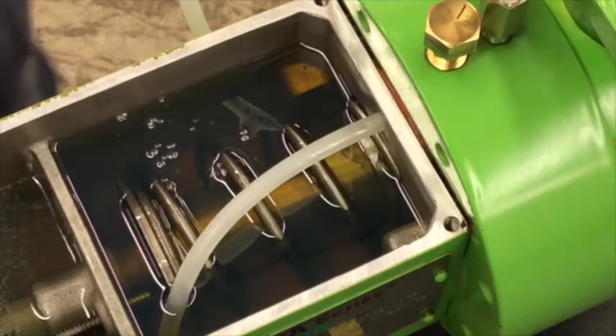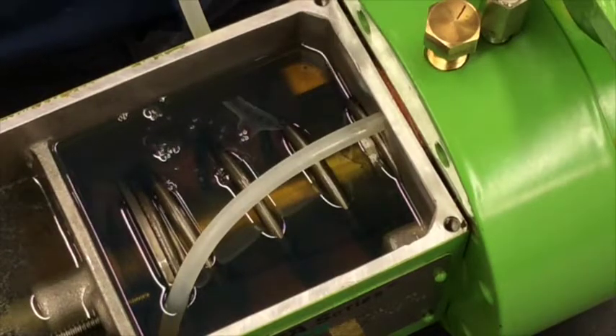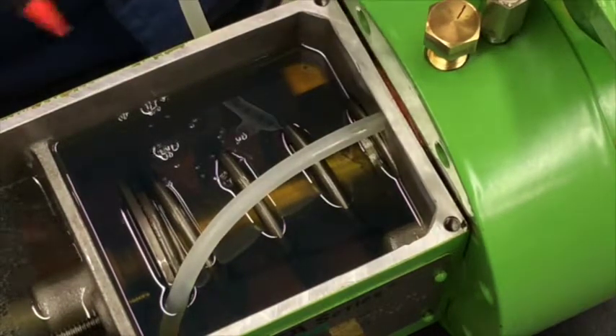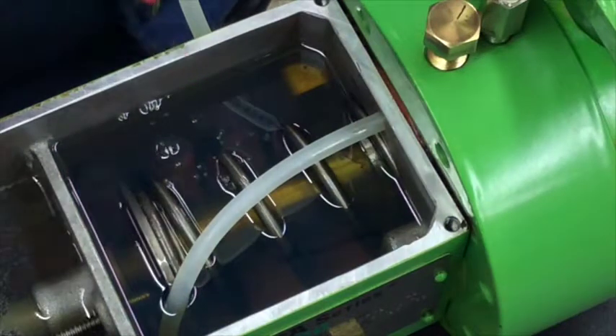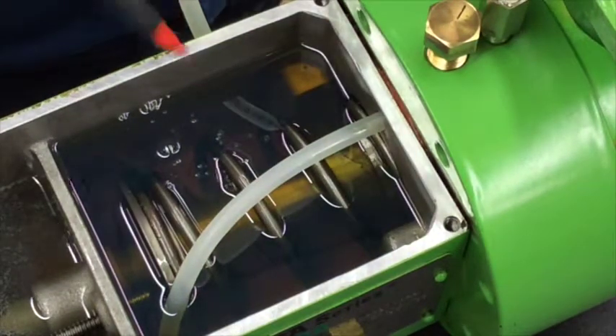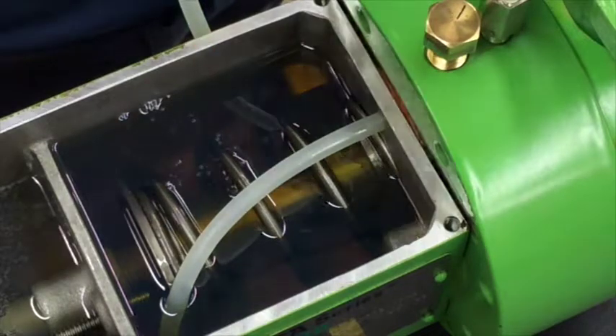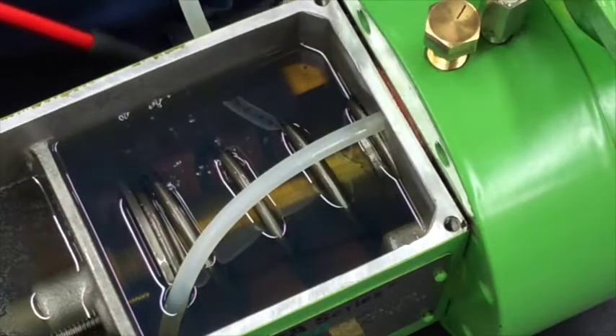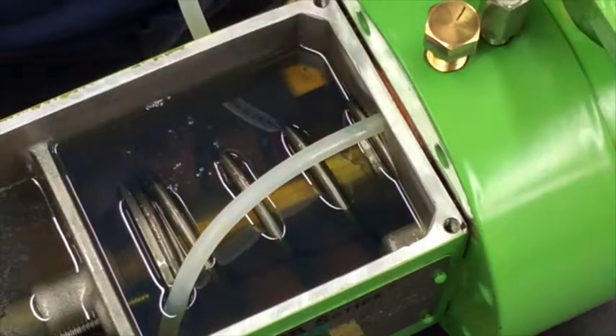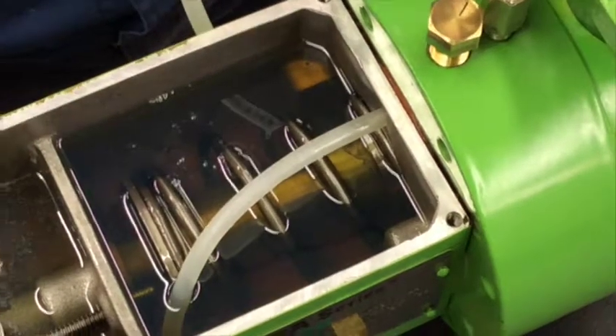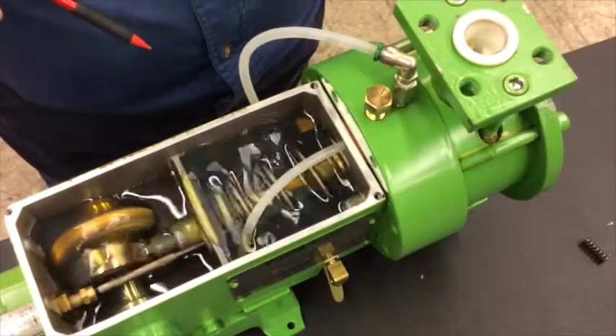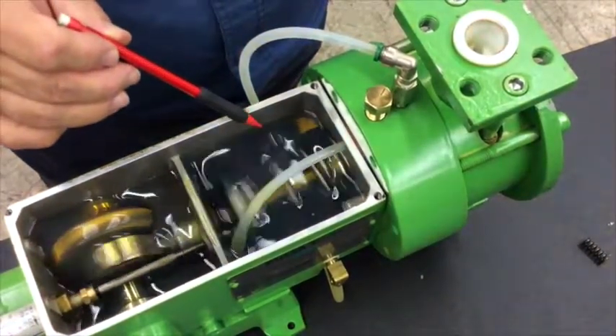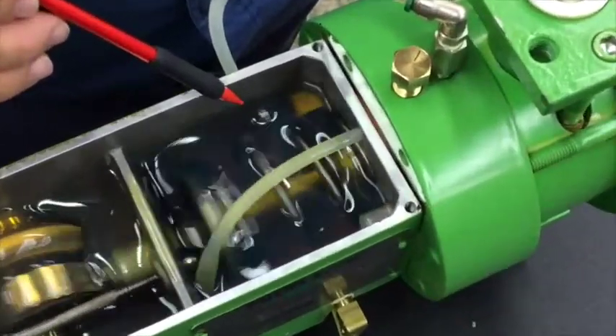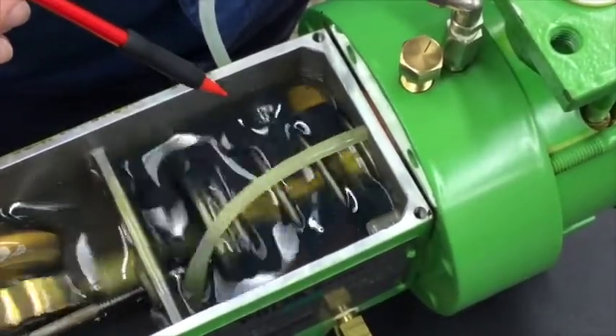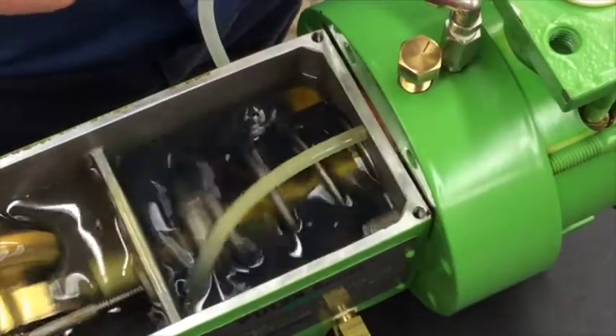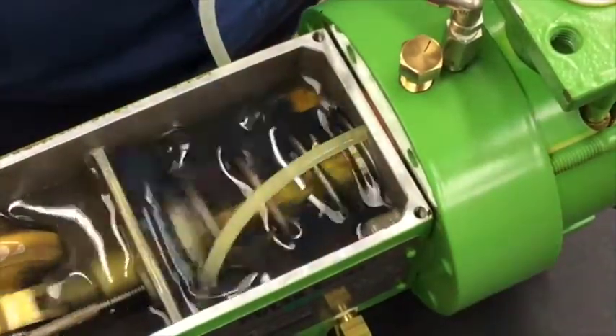Great. Now, what we're also going to note is we want to observe the action of the air bleed valve. And I think when we run the pump, we should be able to observe air being pumped back into the pump via this tube that goes down around the bottom of the chamber here. So my colleague will start the pump. And there's some bubbles right there. So that's telling me that the air bleed valve is working. Okay. Air is being bled out of the valve here, back through the tube and into the chamber.